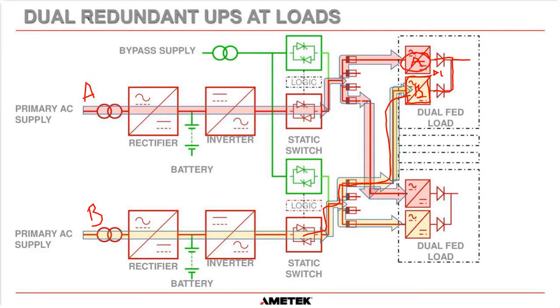And then usually it's 24 volts DC that comes out of these power supplies, but it could be 48 or 12, depending on the system that you bought. Usually this is for DCS systems, distributed control systems, where they have the ability to accept usually 3 different AC sources for the DCS panel. You can have one fed from the grid, one fed from UPS-A, and one fed from UPS-B, and therefore you have a very robust system, and your DCS will remain powered in most circumstances. Hopefully I explained that okay.